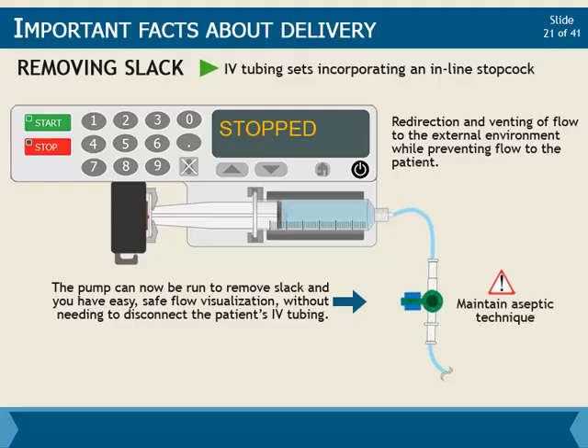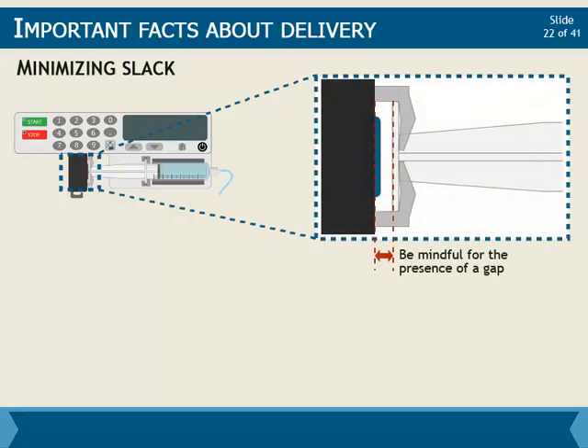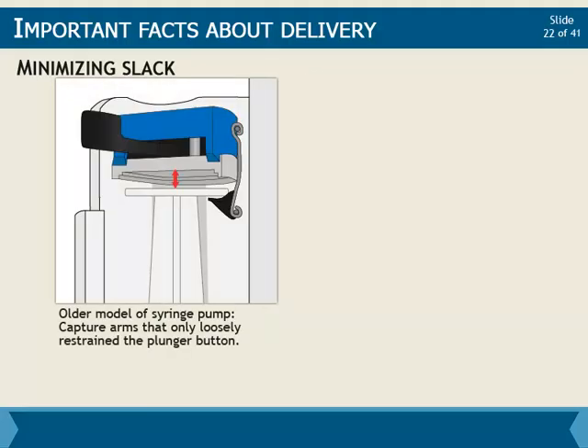Another way to help minimize slack is to be mindful for the presence of a gap between the syringe plunger button and the pushing drive. Historically, some older models of syringe pumps had capture arms that only loosely restrain the plunger button, allowing for a significant sized gap.